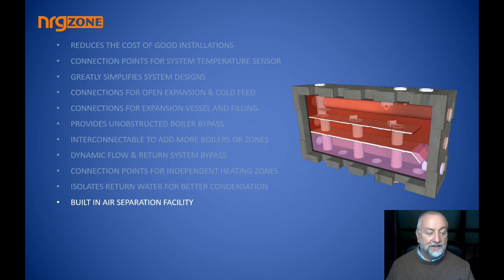And then the built-in air separation. Air is the arch enemy of heating systems. If you get rid of the air from the system and the system is circulating properly, you're going to find that the gunk that is so prevalent in so many modern systems just doesn't seem to build up at all, because the air is the source of the vast amount of that gunk.